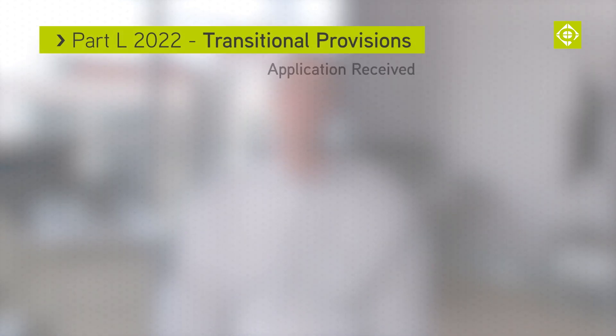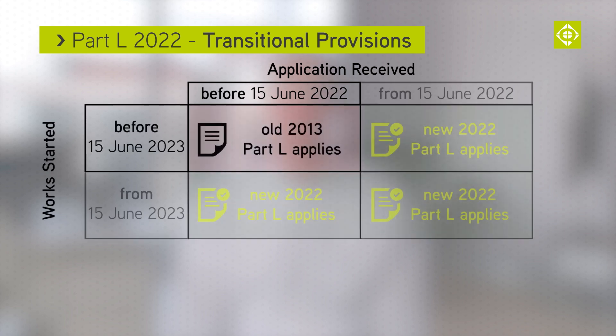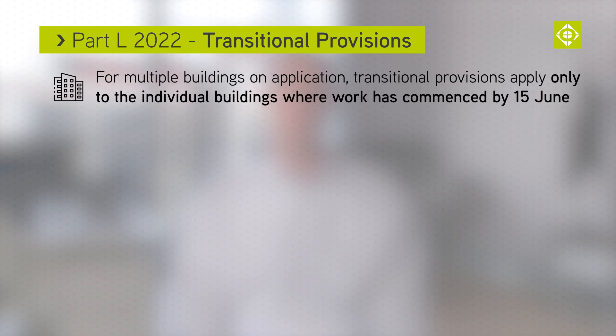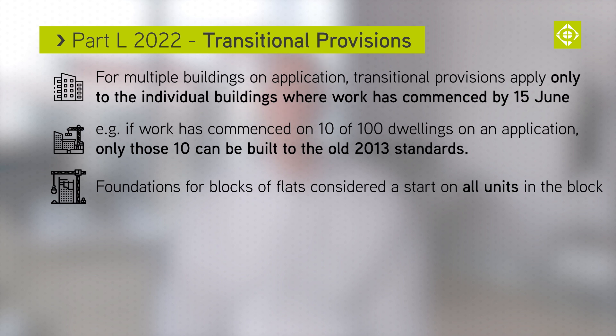Transitional provisions are in place for the new approved documents. To use the old 2013 edition of Part L, an application must be received before 15 June 2022 and work must have started on site before 15 June 2023. For multiple dwellings or buildings on an application, work on each unit must have commenced for the transitional provisions to apply — so for an application of 100 dwellings, work on all 100 units must have commenced before 15 June 2023. If only 10 dwellings have started, only those can be built to the 2013 standards; the remainder must meet the new 2022 standards. Foundations for blocks of flats are considered a start on all units within that block.